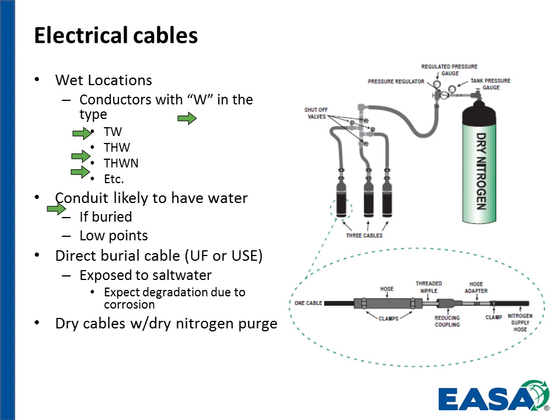If we have conduits run underground, they almost certainly have water in them. So that's going to have to be blown out with due diligence paid to the other end of the conduit, so we don't blow 500 gallons of water through and soak the motor control center and cause all sorts of other issues. Direct burial cable will be designated UF or USE. And if it's exposed to salt water, you can expect it to degrade, to deteriorate due to the corrosion.